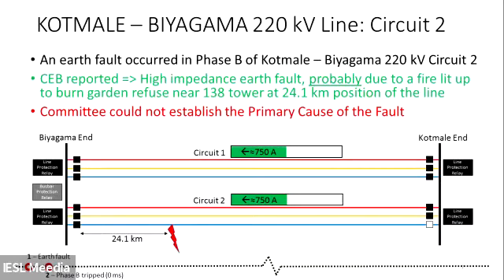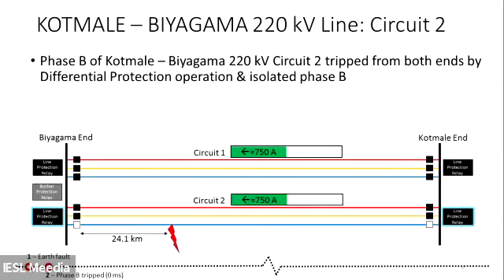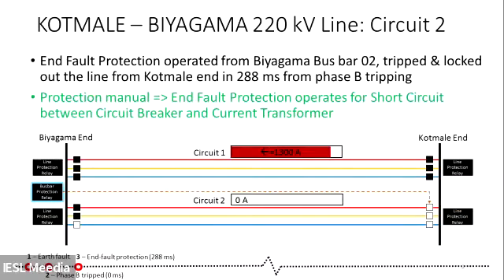From the CEB side, we got to know that it could probably be due to a fire lit to burn garden refuse. But whether this is the exact cause is still not known. This is some evidence that we got. With that, what happened was that the differential protection operated immediately and isolated that fault. And what happened next was, 288 milliseconds later, the complete line, circuit 2, was disconnected by the operation of the end-fault protection, right?